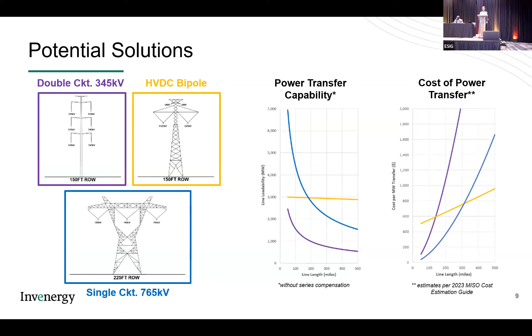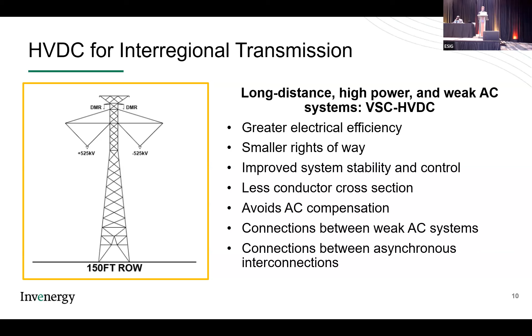Another piece is the electrical efficiency with long distance, avoiding the need for AC compensation. That's where the economics start to favor HVDC. You also get a lot of system benefits with HVDC, things like reactive power and power flow control are inherent to the technology, and it's become a preferred solution for these long distance interregional projects. Also, for asynchronous interconnects in the US, HVDC is the option there as well.